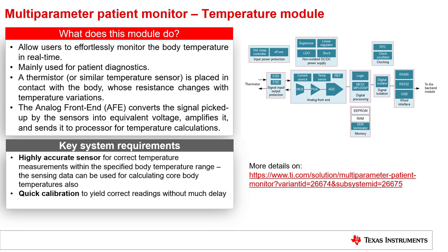The key requirements for the temperature module are: a highly accurate sensor for correct temperature measurements within the specified body temperature range — the sensing data can also be used to calculate core body temperatures — and quick calibration, to yield correct readings without much delay. A common block diagram for such temperature modules is also shown in the slide.